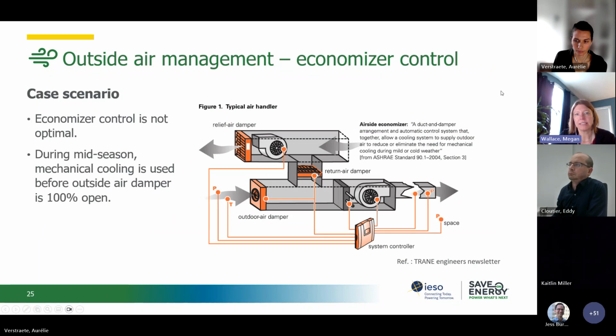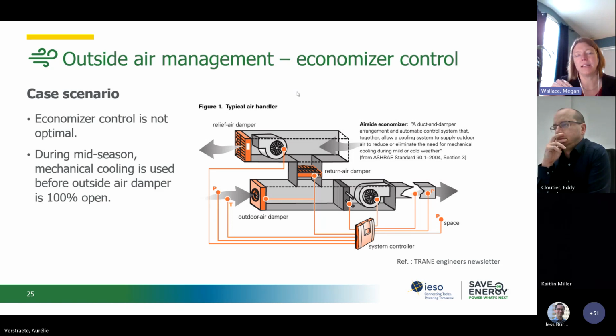So the first scenario we're going to look at is economizer control. The schematic shows a typical air handling unit that has outdoor air being brought in and a mixed air damper or return air damper to control how much outdoor air goes into the system and how much exhaust goes out. To optimize the economizer, we would increase the amount of outdoor air that we're bringing in when the outdoor air temperatures are optimal. So this is usually in shoulder seasons when we have cooler days and we need cooling on the inside of the building, and we can optimize bringing in more outdoor air to provide free cooling.